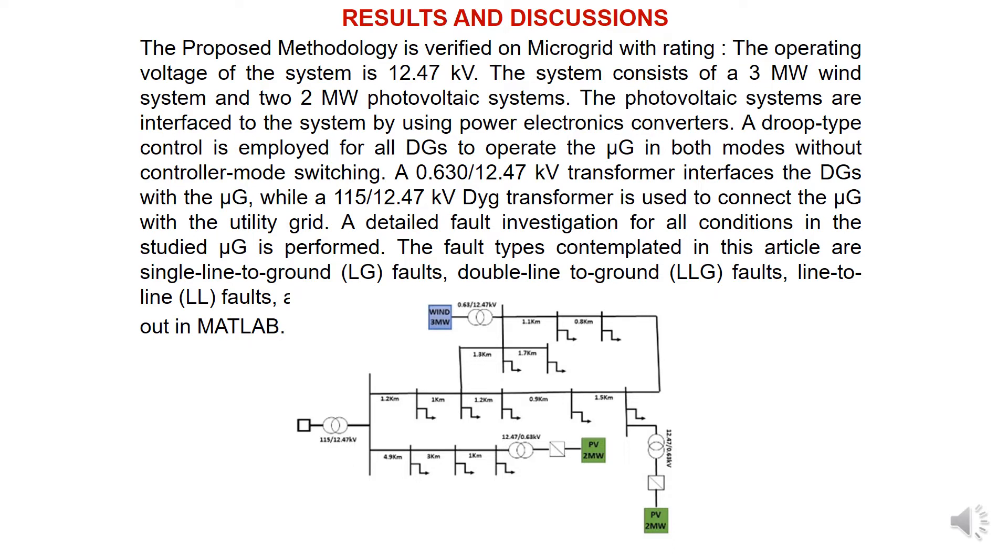The photovoltaic systems are interfaced with the system using power electronic converters. A droop-type control is employed for all distribution generation to operate the microgrid in both modes without controller mode switching. A 0.630 by 12.47 kV transformer interfaces the DGs with the microgrid, while a 115 by 12.47 kV transformer connects the microgrid with the utility grid.